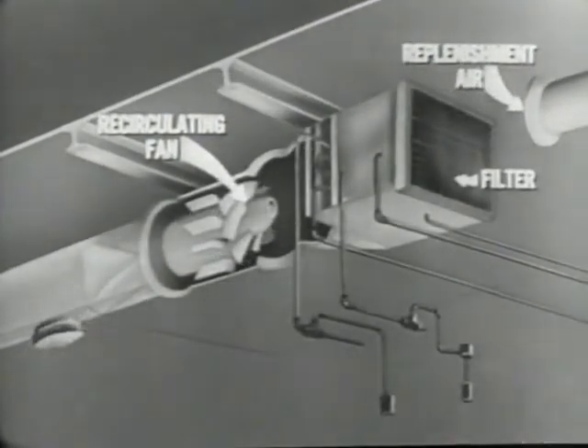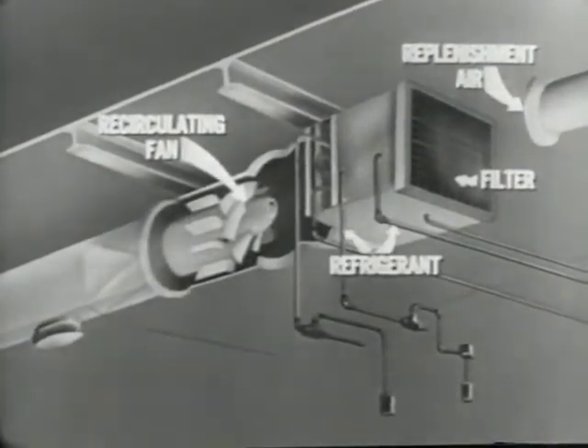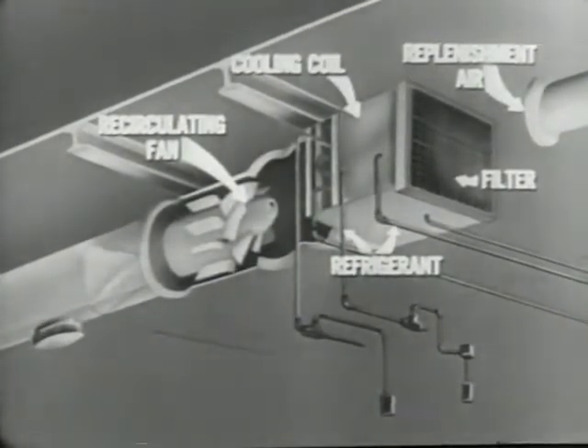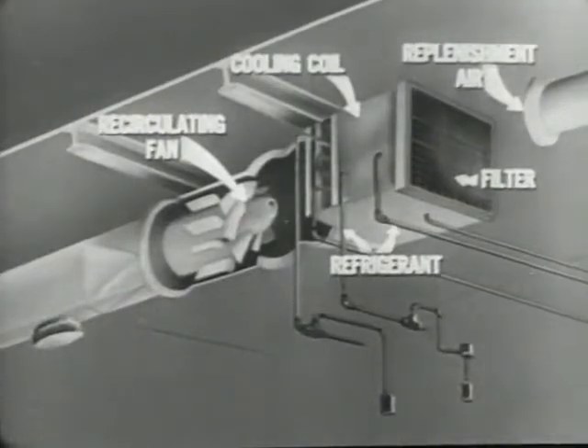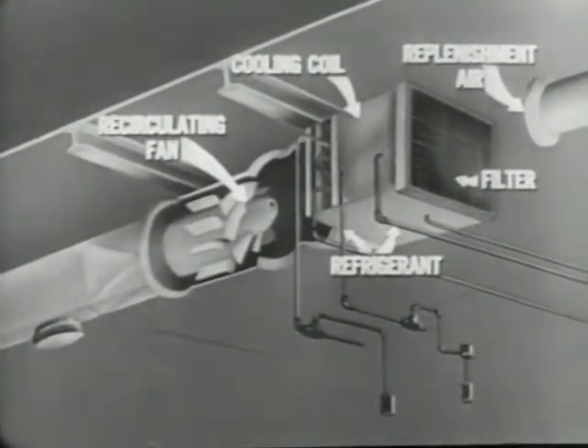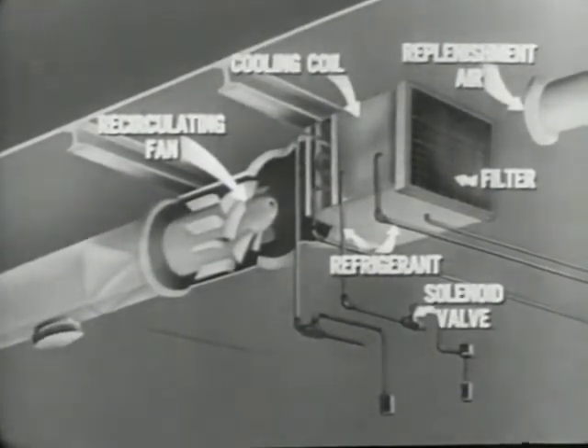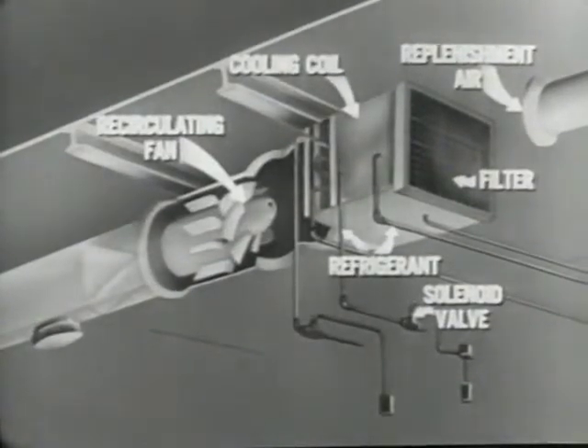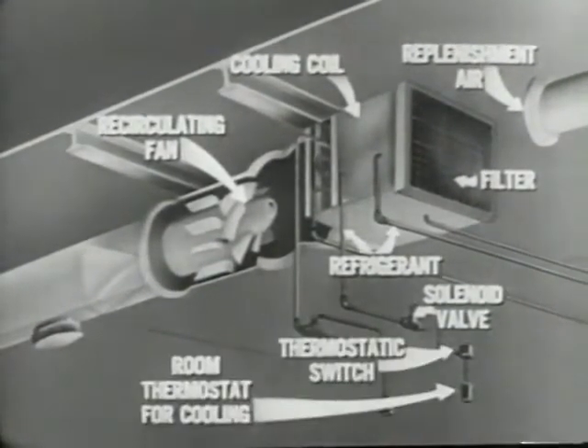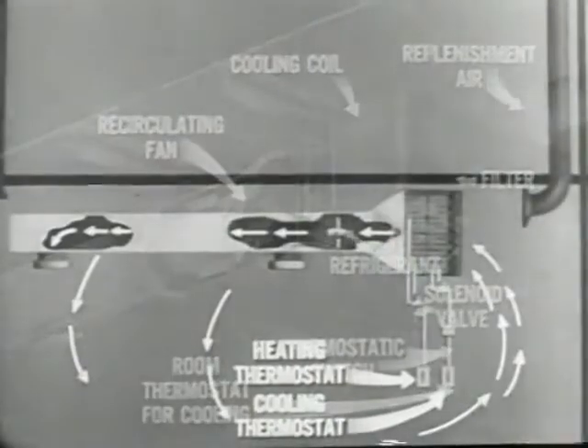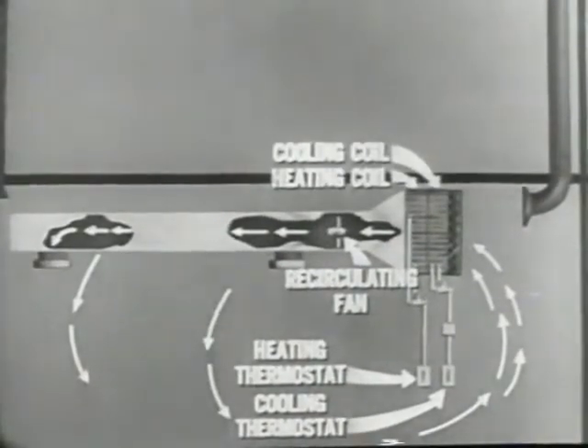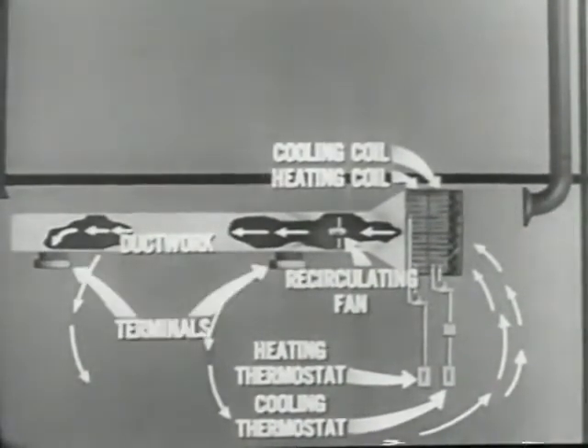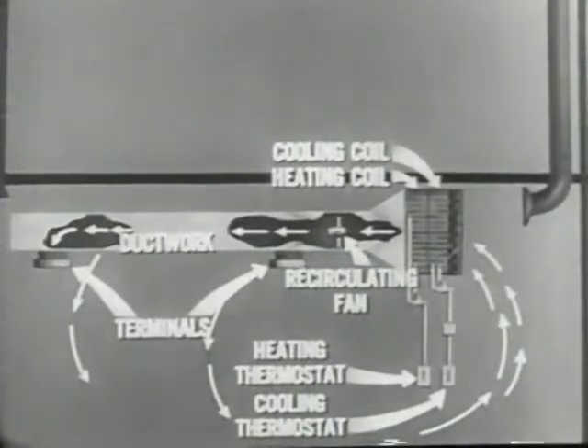Cooling is accomplished by circulating a refrigerant, such as Freon or chilled water, through the cooling coils. The refrigerant is supplied from a centrally located refrigeration plant, and its flow to the coil is regulated by a solenoid valve controlled by a room thermostat. The fan moves the air past the coils, through the ductwork and terminals, and circulates it throughout the space. This cycle is repeated continuously.